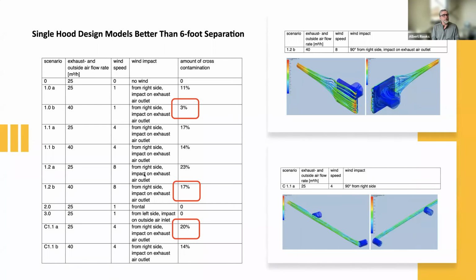In 1.2 down there, that's the same hood in the worst condition. There's a potential of 17% while it's in those conditions. That matches the 6-foot separation, which is design type C. And in that same condition, it's 20% and 14%. So these hoods in many conditions perform better than 6-foot separation. And you can see we're comparing kind of like to like, the worst possible situation where the airflow is kind of going one past the other.